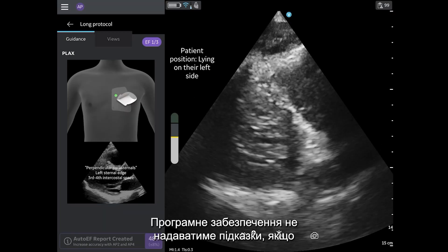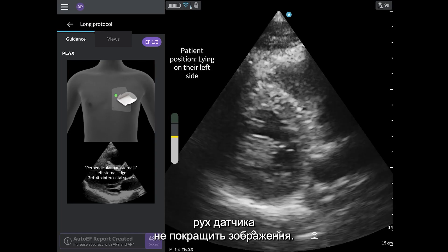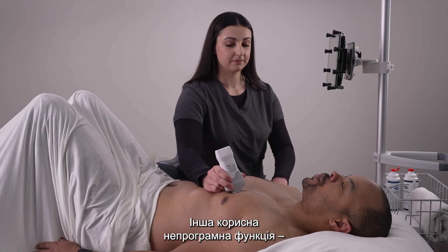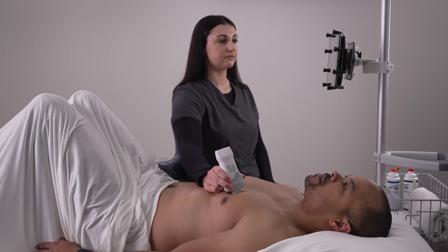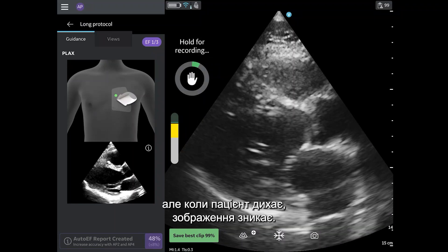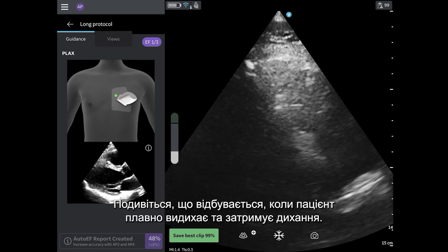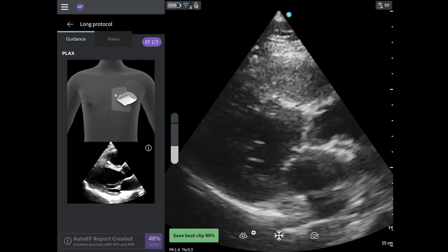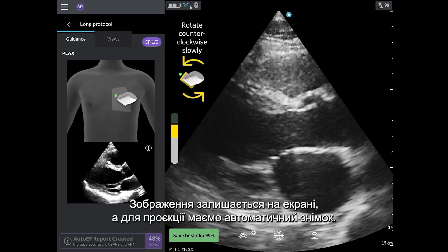The software will not prompt guidance if it is not confident that a probe movement will improve the image. A non-software feature that is helpful in this case is knowing when and how to control the patient's breathing. In this example, the quality meter gets close to auto-capture, but when the patient breathes, the image disappears. Watch what happens when the patient gently exhales and holds their breath out — the image remains on the screen, and the view can be auto-captured.